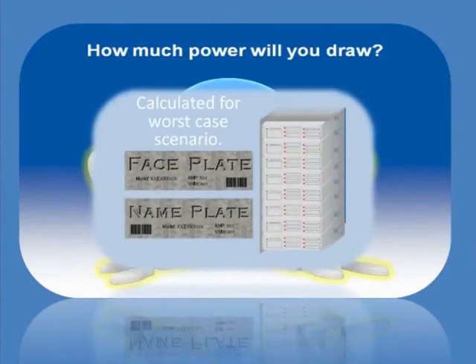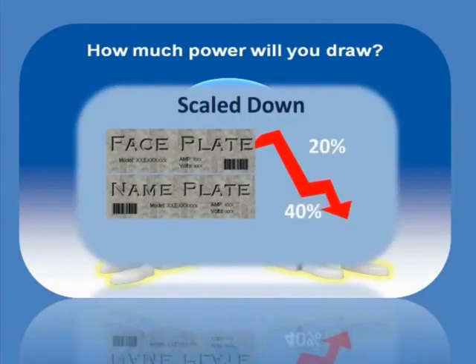Equipment manufacturers provide a nameplate or faceplate power ratings. These ratings are often calculated for a worst-case scenario. In reality, actual day-to-day power draw is often much less. Some IT departments take faceplate ratings and scale down from 20% to 40% when factoring in power.